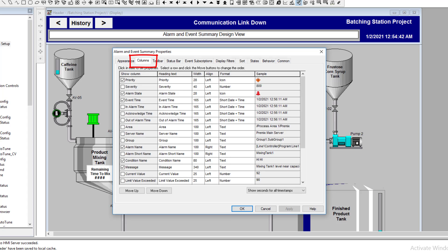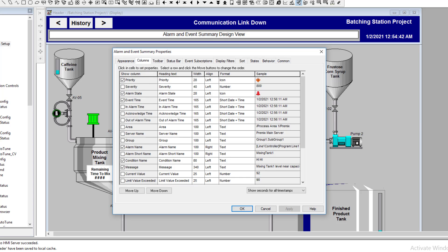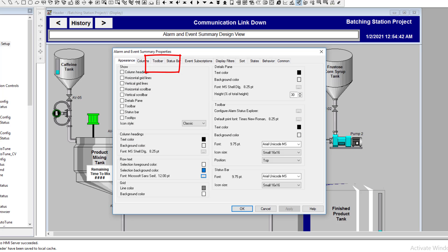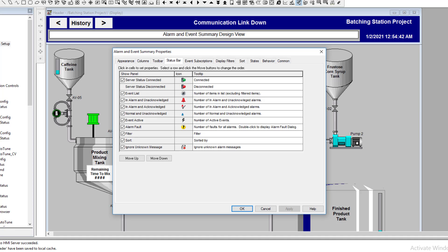Now in our Columns settings, we really only want two things: we want to know the time the alarm happened — so Event Time is critical — and we want the Message. We don't really care about Priority. So we'll check those two boxes. For Toolbar, that's completely fine; we'll leave it since we already eliminated that elsewhere.